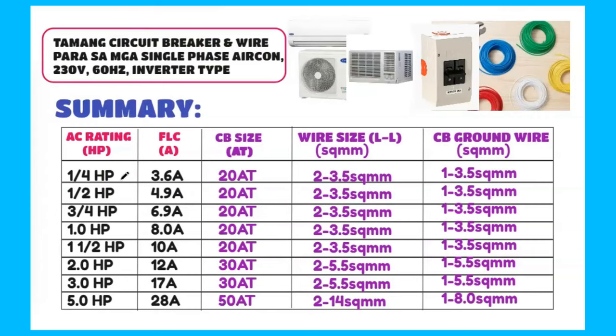So, ito is summary na kung ano yung napag-usapan kanina. Computations, gamit ang table, saka yung sa PEC code. So, lumalabas, itong 1/4 HP hanggang 1 1/2 HP, ang circuit breaker size niya is pasok siya sa or pwede mong gamitin ang 20 ampere trip. Yung size of wire pwede ang dalawang 3.5 square mm. Saka itong ground wire mo is isang 3.5 square mm.